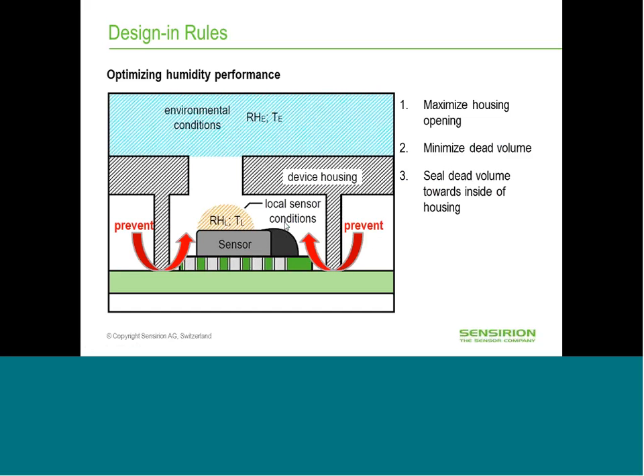As a third rule, it's important to seal the dead volume towards the inside of the housing. You have to prevent air from the inside of the housing from going into the dead volume and to the sensor, because the air trapped inside the housing will change very slowly to changes of environmental conditions. If you always have a little air from inside the housing going to the sensor, there will always be a disturbance. So this has to be sealed as well as possible towards the inside of the housing.